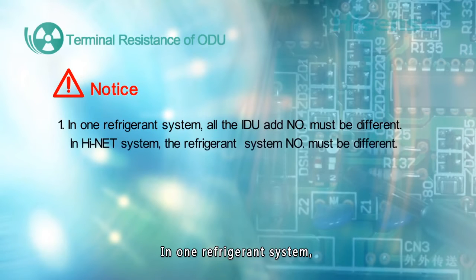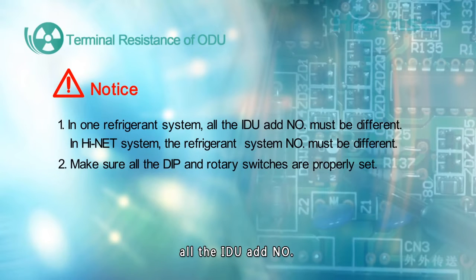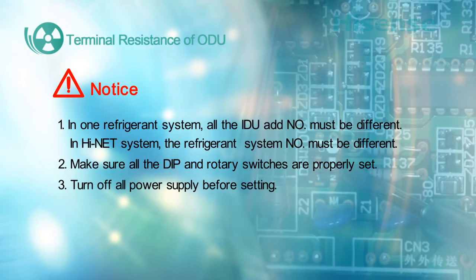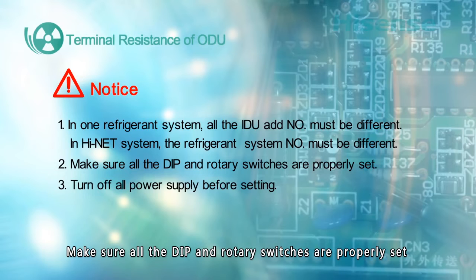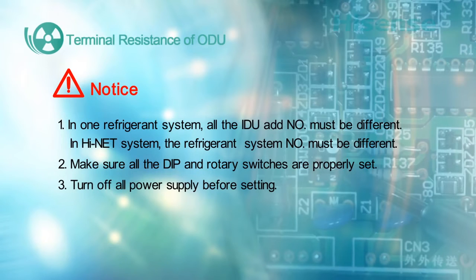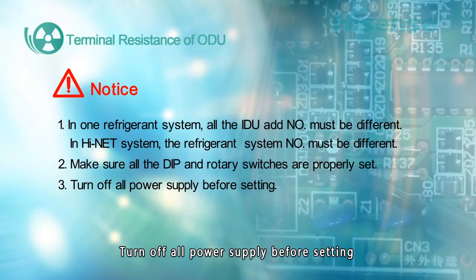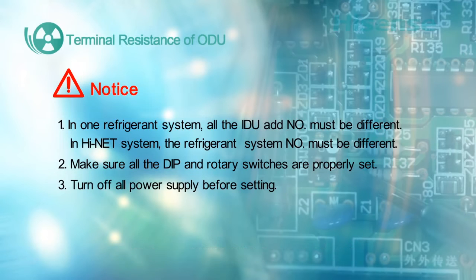Notice: 1. In one refrigerant system, all the indoor unit address number must be different. In Hi-NET system, the refrigerant system number must be different. 2. Make sure all the dip and rotary switches are properly set. 3. Turn off all power supply before setting.